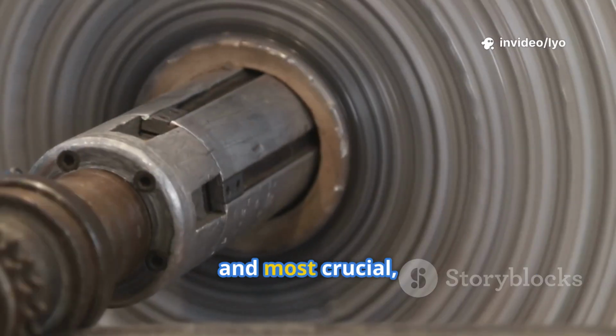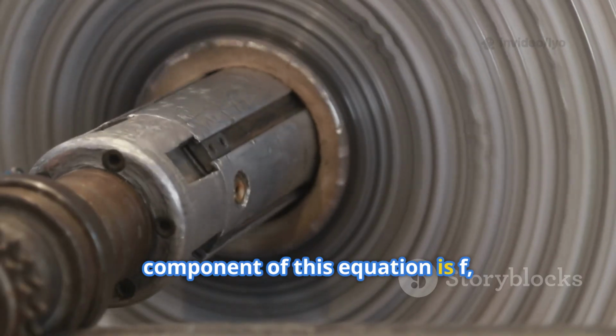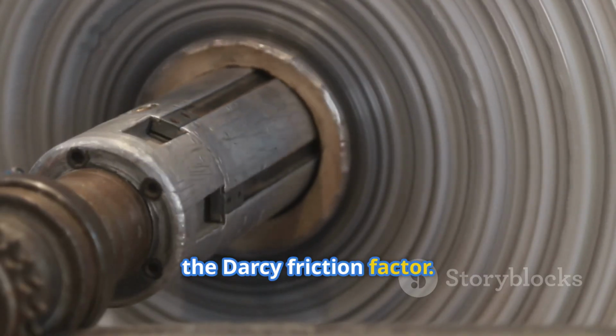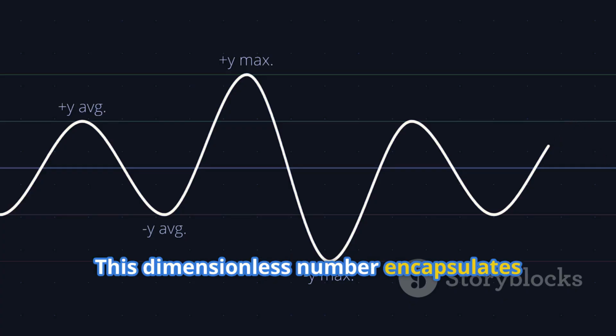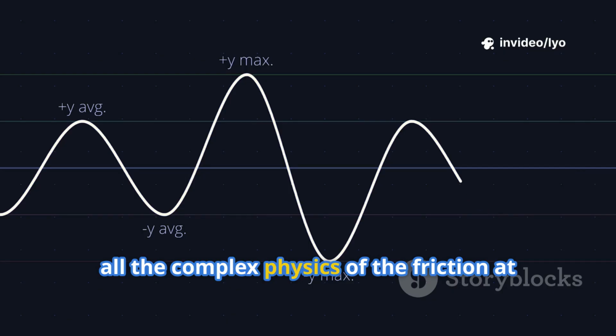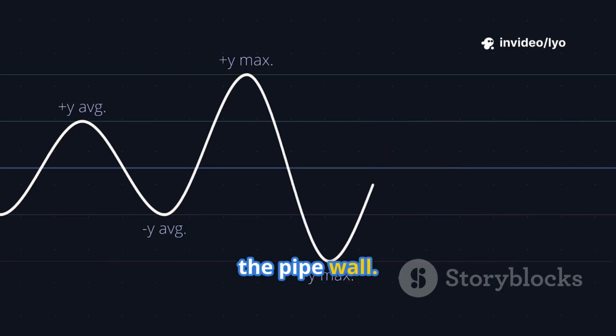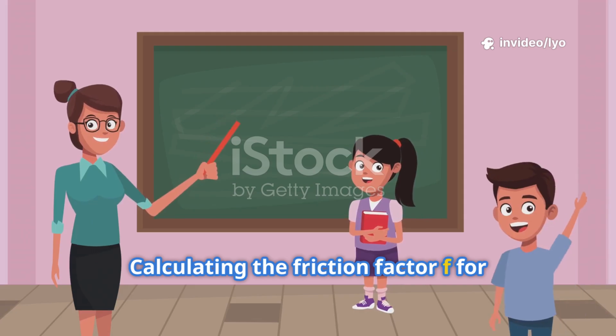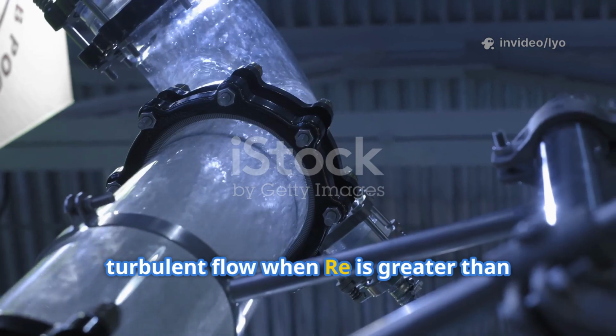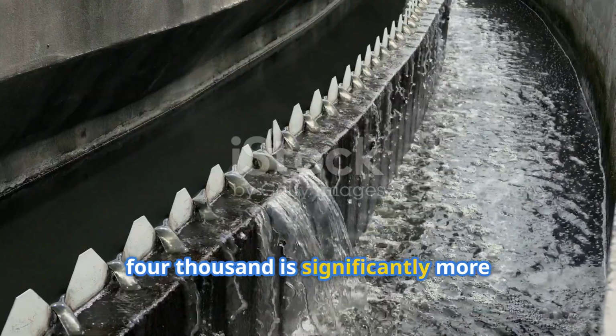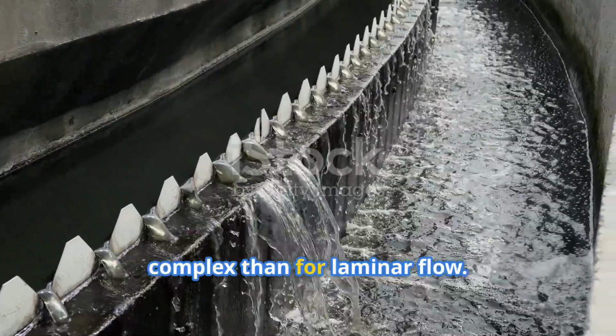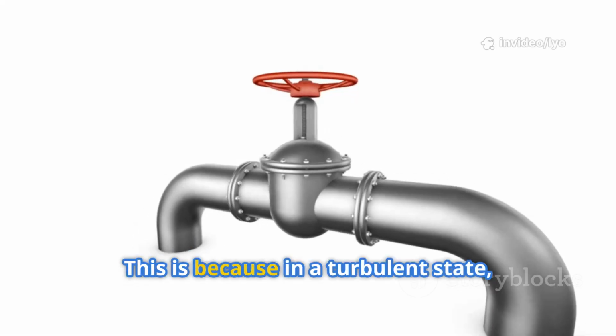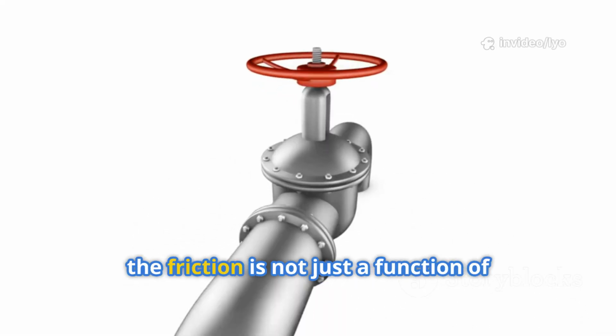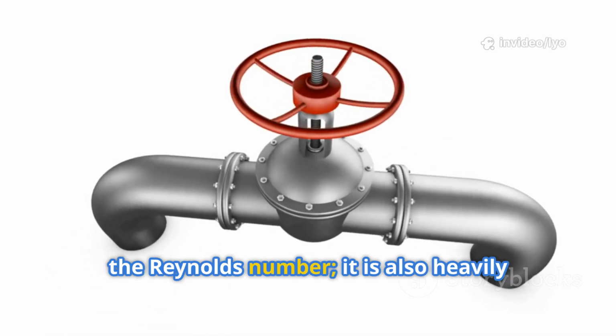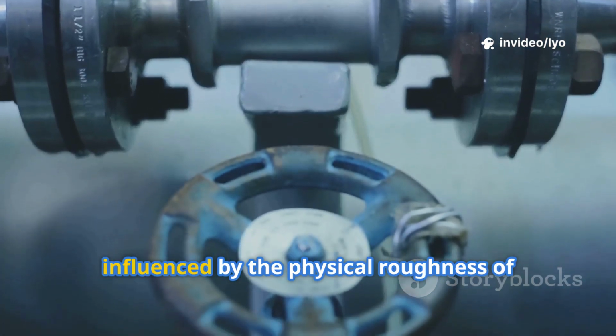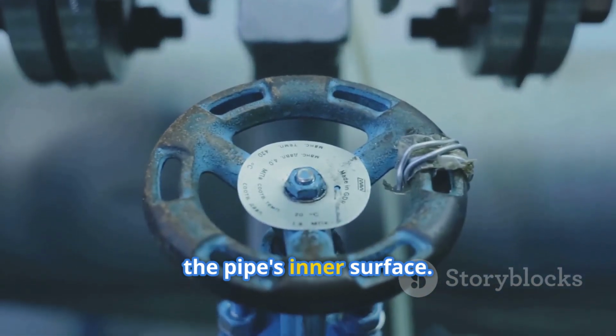The final and most crucial component of this equation is F, the Darcy friction factor. This dimensionless number encapsulates all the complex physics of the friction at the pipe wall. Calculating the friction factor F for turbulent flow, when Re is greater than 4000, is significantly more complex than for laminar flow. This is because, in a turbulent state, the friction is not just a function of the Reynolds number. It is also heavily influenced by the physical roughness of the pipe's inner surface.